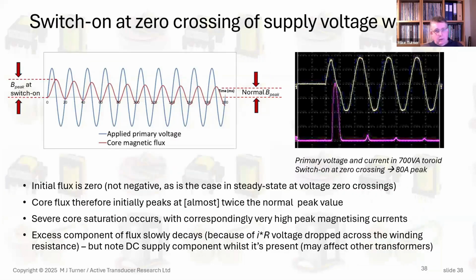Another gotcha in low frequency power supplies is the switch on. If you switch on at the zero crossing of the mains, then what happens is you've got the whole half cycle at the start to build up the field, and the flux density builds to twice the normal working value, because it doesn't start from the steady state, where it starts from a negative value. At switch on it doesn't, and we end up with this transient of flux, this standing DC component of magnetic flux in the transformer that gradually decays away with the winding resistance driving that down. If you switch on a mains transformer, you'll have heard it yourself. You go dong, and the whole case of the amplifier shakes a bit as you go through this transient.